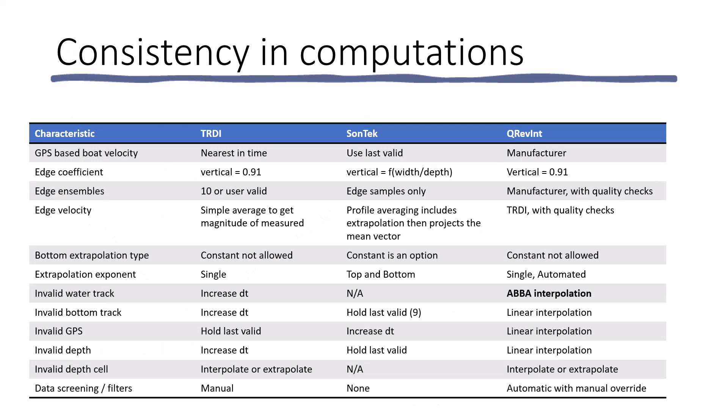So, I mentioned consistency, and you would think that you want consistency in computations. If you had the same data and you could process it both in TRDI's WinRiver 2 software and Sontek's River Surveyor Live software, you would expect that you should get the same discharge. However, when we look at the methods used by both pieces of software, we see a lot of differences, as these are shown in this table. And a couple of the major ones that I see is if you have invalid data. And what happens if you have invalid data?